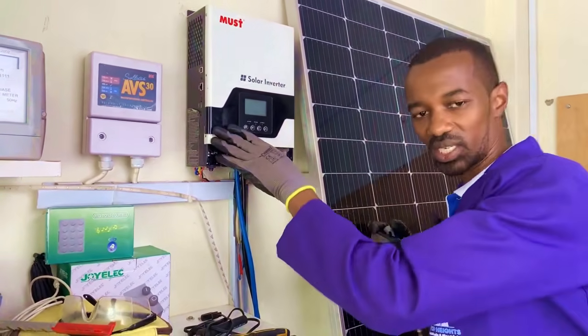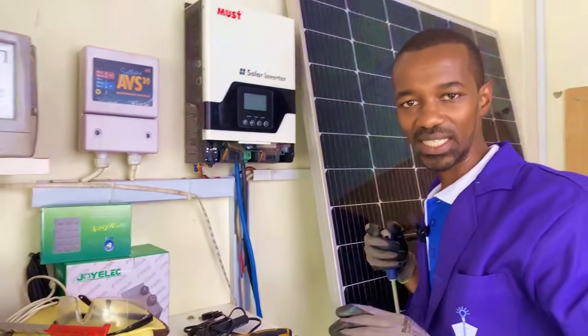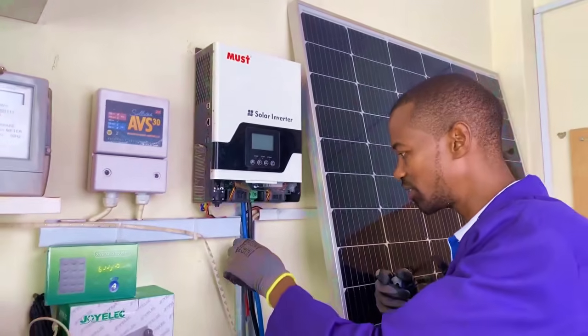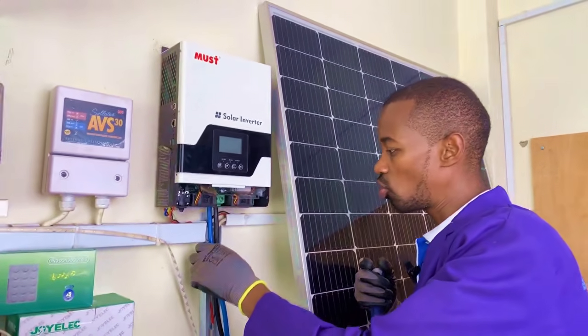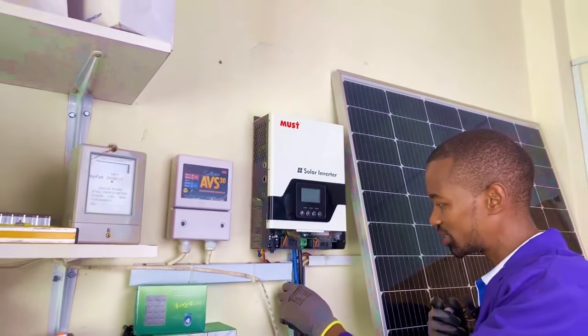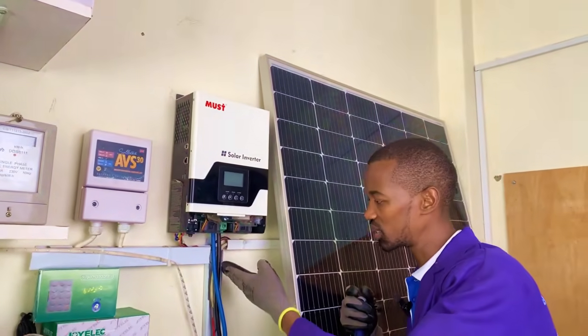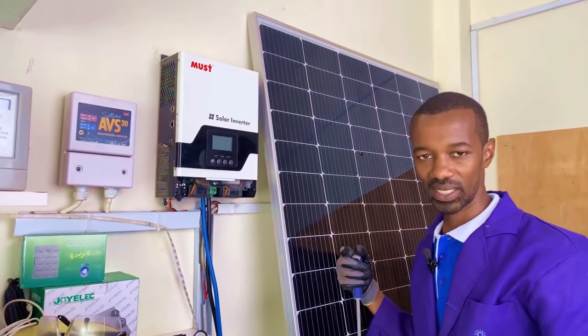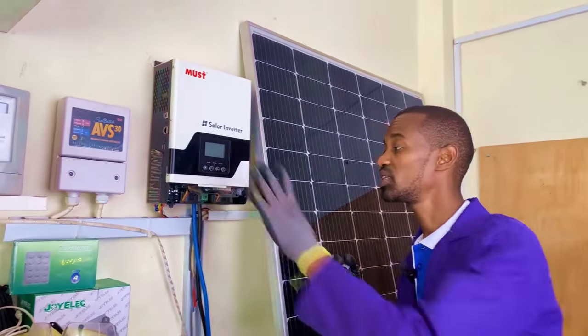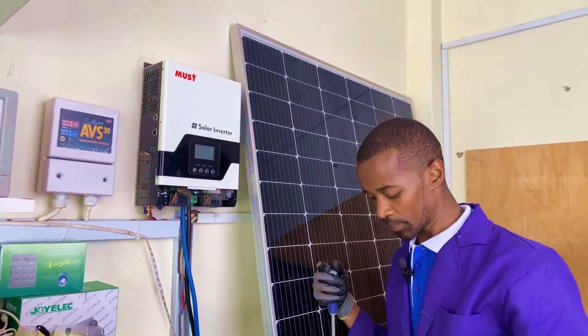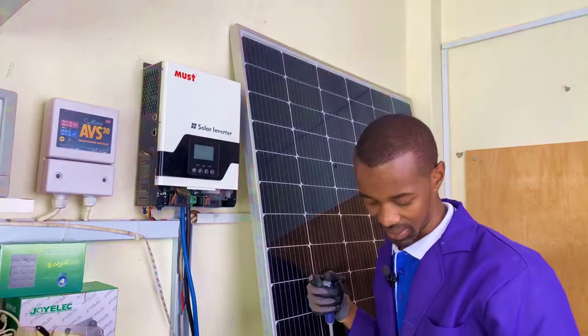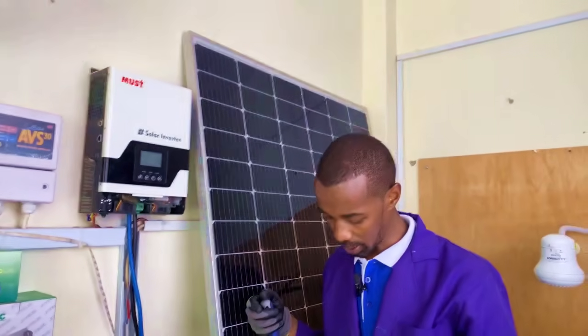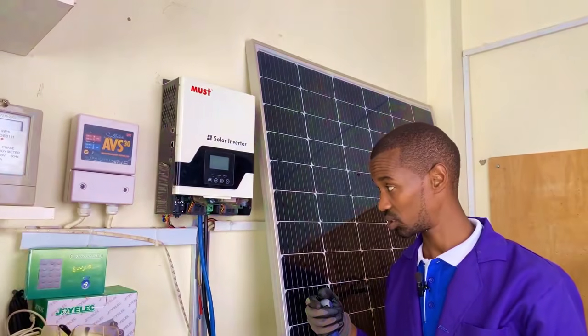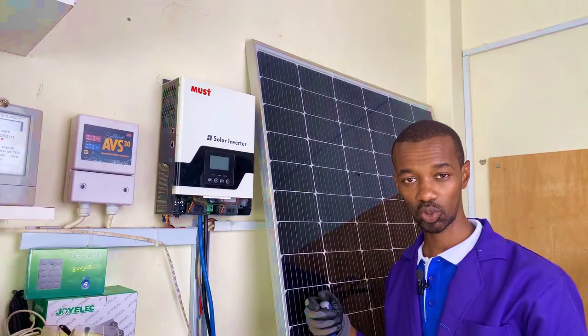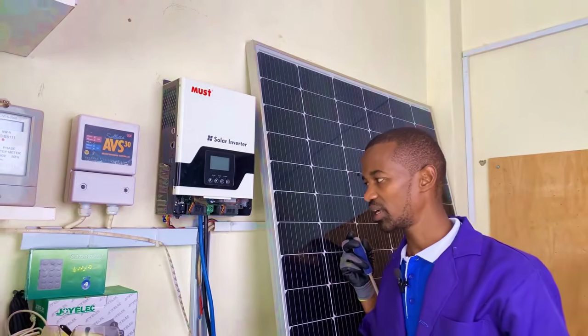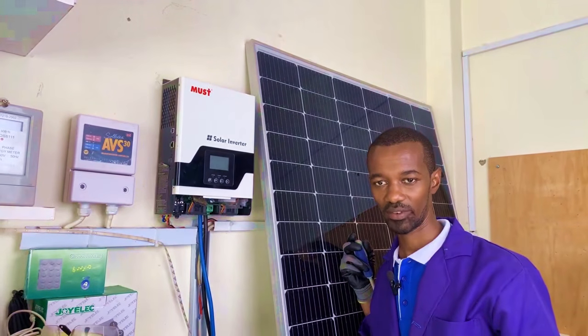Another mistake people make during inverter installation is using undersized cables. For instance, using a very small size like 2.5 for battery cables will cause them to overheat, because the current exchange between the inverter and battery is usually very high. With a 12 volt battery rated at 200 amp hours, it can give out 200 amperes in one hour — that's a very high current, so you must be very keen.